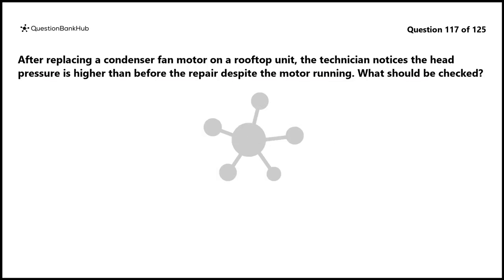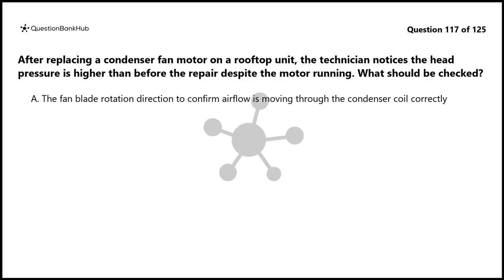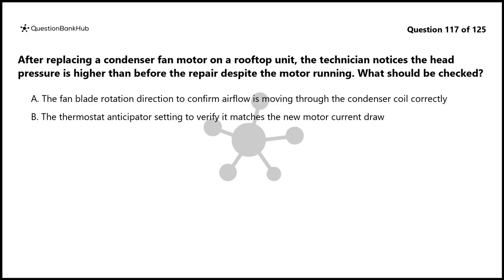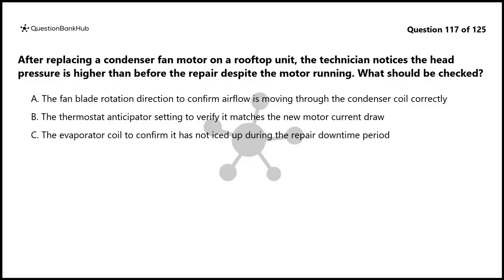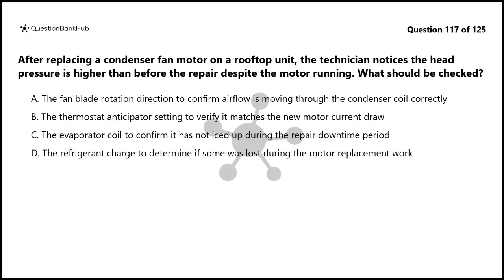Question 117. After replacing a condenser fan motor on a rooftop unit, the technician notices the head pressure is higher than before the repair despite the motor running. What should be checked? A. The fan blade rotation direction to confirm airflow is moving through the condenser coil correctly. B. The thermostat anticipator setting to verify it matches the new motor current draw. C. The evaporator coil to confirm it has not iced up during the repair downtime period. D. The refrigerant charge to determine if some was lost during the motor replacement work.